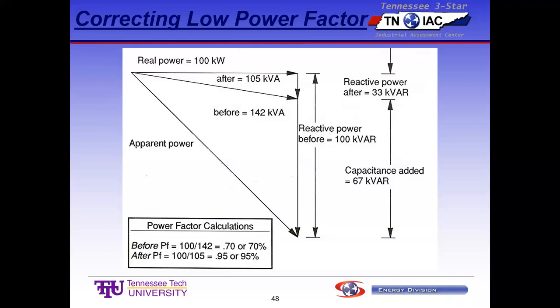The big savings are getting out of penalty. If you go on up, you're only going to save the I squared R, because you will reduce the current a little bit more. Absolutely you will. You can do that, but once you get to 95, then no penalty. And let me show you.